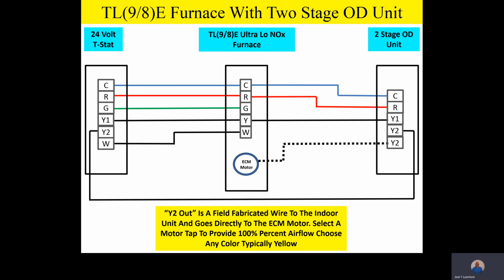One final note about the ECM motor that you've noticed that, we could have a G call to the motor. We could have a Y1 call to the furnace, and it tells the motor what to do. We could have a Y2 call going to that ECM motor. The point is, one of the great things about the ECM high efficiency motor is if it receives more than one speed command, let's say it has a G call and a Y1 call and a Y2 call, that's perfectly okay. It's not going to hurt the motor. That motor is designed that if it has more than one 24-volt speed command, it always drives that fan to the highest speed that it's receiving. So we call that airflow priority. So that fan motor is actually commanding 3 speeds in this example, G, Y, and Y2, but that's okay because it will always take the highest of those commands and drive the motor to that speed.